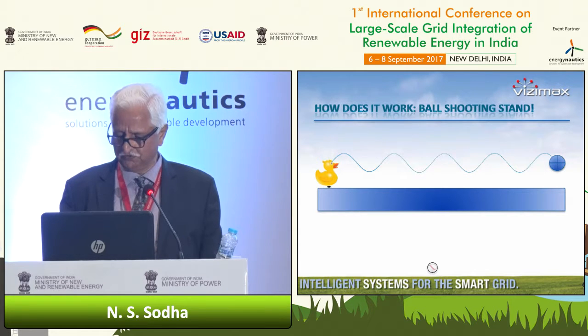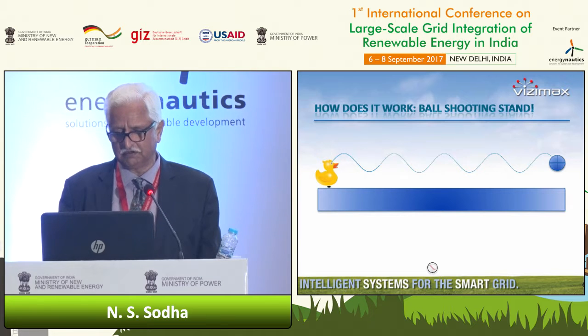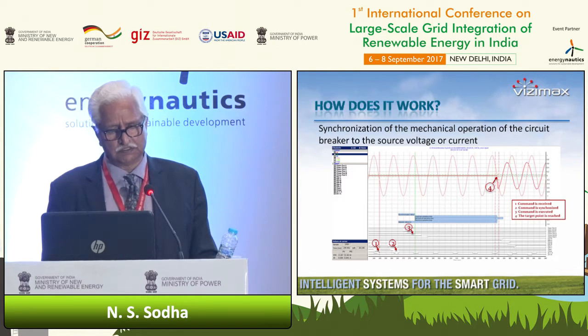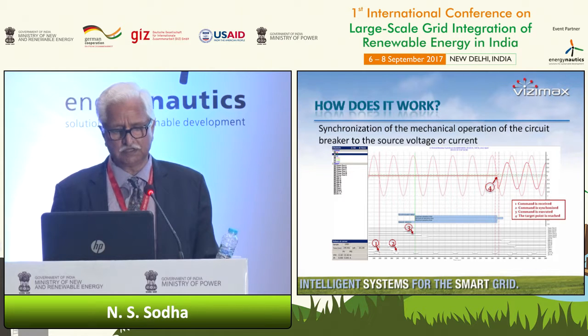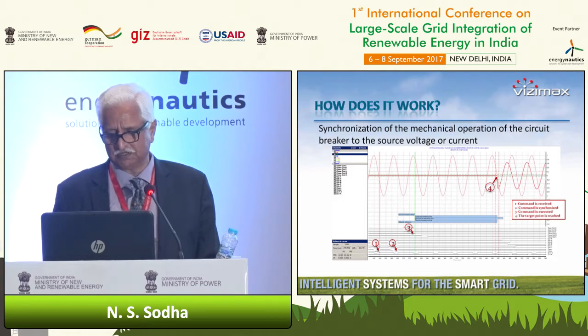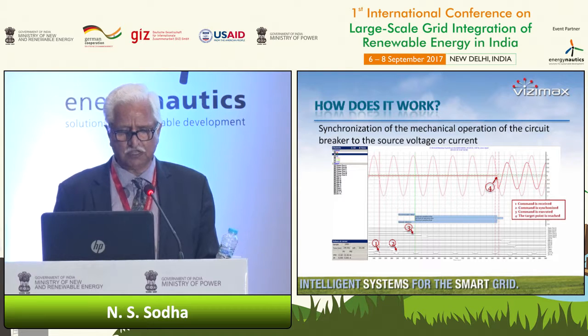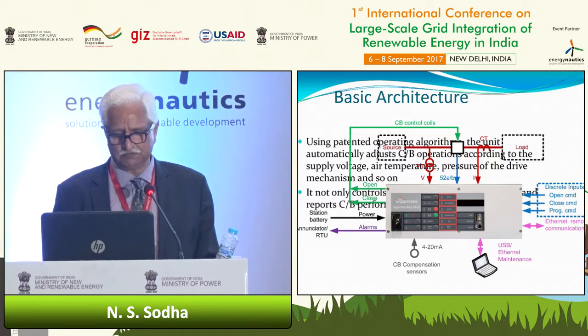I'll just play it again for you. The waveform has to be hit like this at the right moment when the breaker is operating. How does it work? By synchronization of the mechanical operation of the circuit breaker to the source voltage or the current. These 4 points, which are indicated as arrows on the graph here, are the points where you have to hit and you have to measure. And those are the issues that we are talking about in controlled switching.